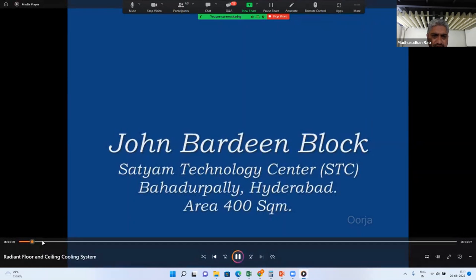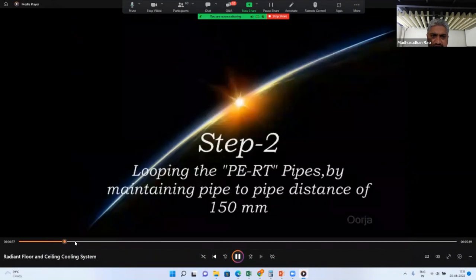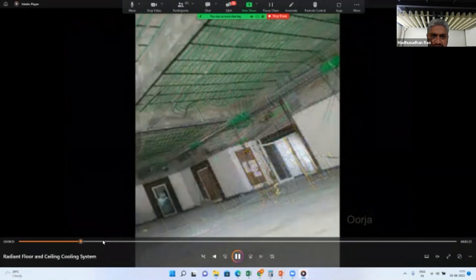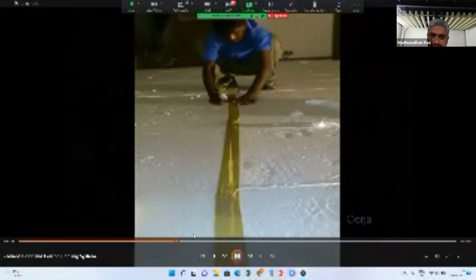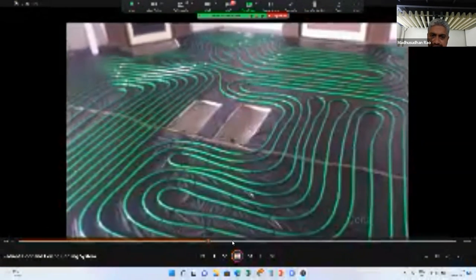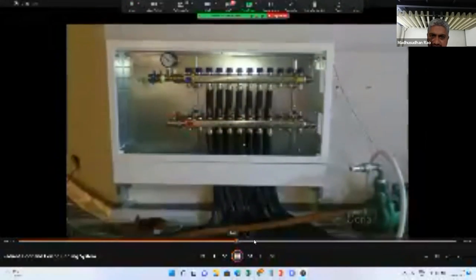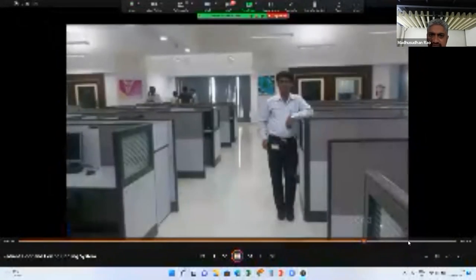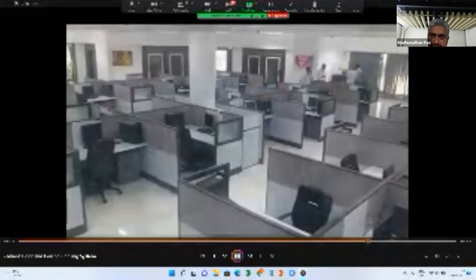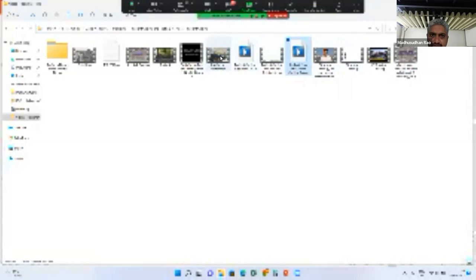So this is the project for which I had shown some data. This is the project where we had done it on the ceiling. The entire pipes were put on the ceiling, then pressure tested. When everything is okay, we plastered it, connected it to the manifolds. Then another block where insulation was put, and then pipes were installed. Again, pressure test. Connected to the manifold. If everything is okay, you lay the screed and then the tiles, and this is the final space. So slab cooling, ceiling cooling, floor cooling, and this is the warehouse where radiant panels are installed.